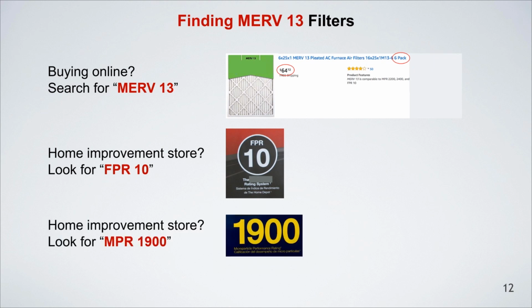Then there's another system by one of the filter manufacturers, also proprietary, called the Microparticle Performance Rating, the MPR rating. And if you were to look at filters made by that manufacturer, and if you look for an MPR 1900 or maybe a 1700 even, either one of those would give you effectively a MERV 13 or better rating. So those are the 3 things that you want to look for online. A MERV 13 is easy to find at home improvement stores. Either an FPR 10 or an MPR 1900 is going to get you the filter that you'd like to have. You can get better than this, but these are perfectly good choices, and will get a very large proportion of those small particles out using your HVAC system, all dependent, of course, on how many hours your HVAC system is operating.